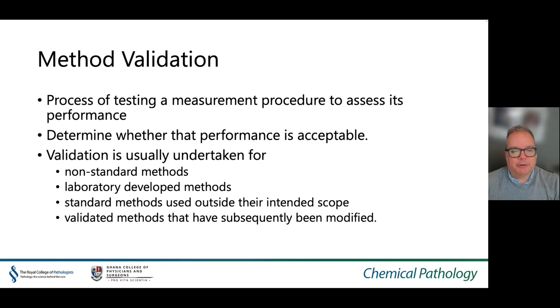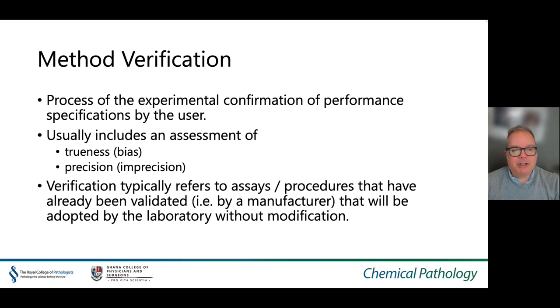Validation is usually undertaken for non-standard methods, laboratory developed methods, standard methods used outside of their intended scope, and validated methods that have subsequently been modified. Method verification, on the other hand, is the process of experimental confirmation of performance specifications by the user, usually including an assessment of bias or imprecision. Verification typically refers to assays or procedures that have already been validated, for example by the manufacturer, and that will be adopted by the laboratory without modification.